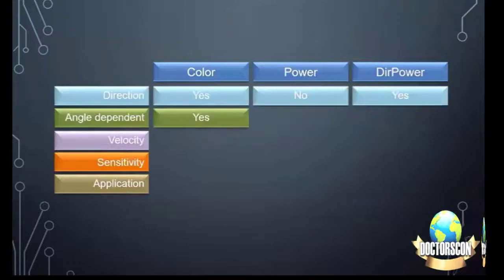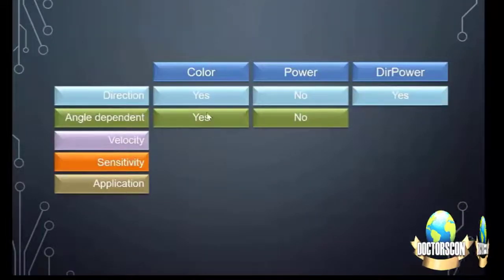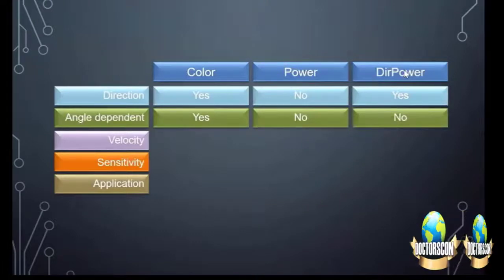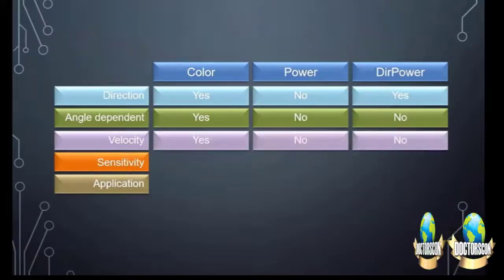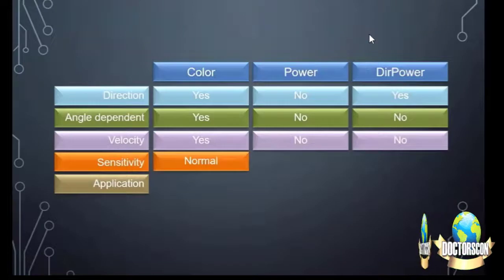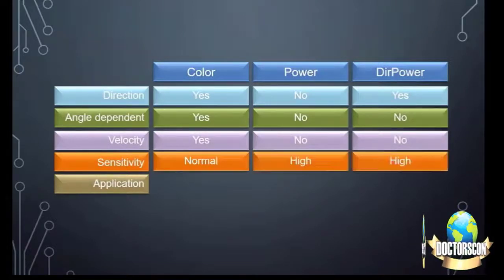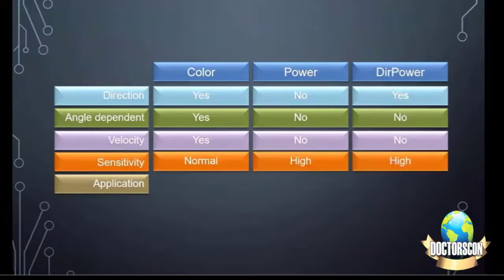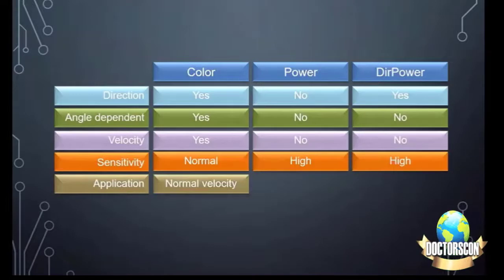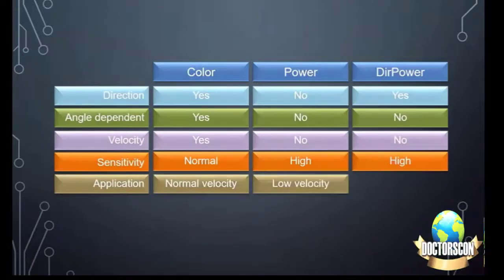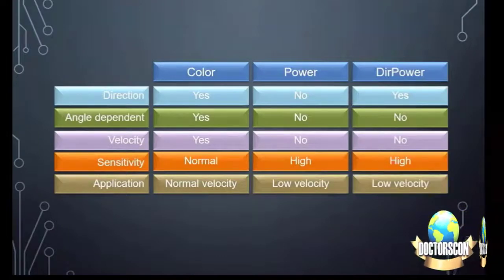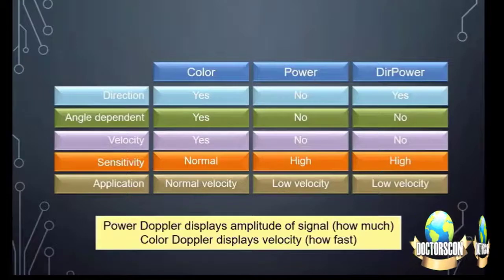Now we come to the difference between color and power. Direction we can detect in color Doppler and directional power Doppler. Color Doppler is angle dependent, whereas power Doppler and directional power Doppler are not angle dependent. Color is dependent on velocity, the other two are not. Color has normal sensitivity, whereas power and directional power Doppler have high sensitivity. For application, color Doppler is used for normal velocity, power is for low velocity, and directional power is for low velocity structures, like small vessels.